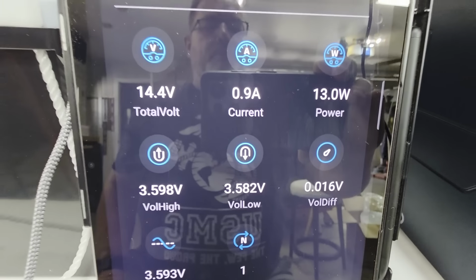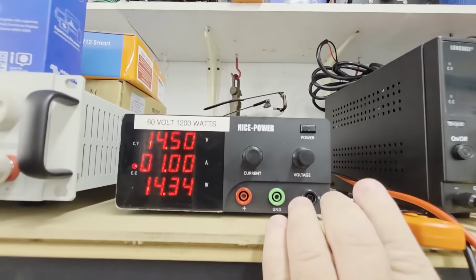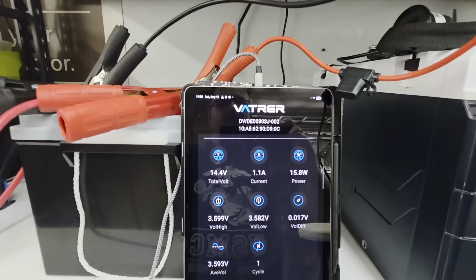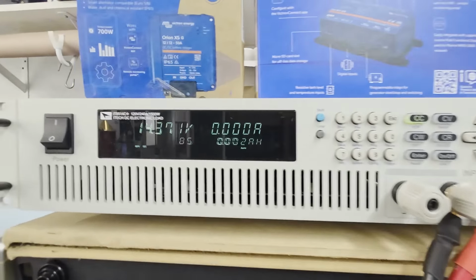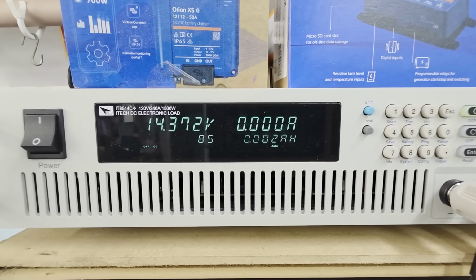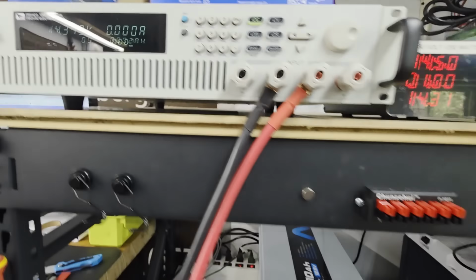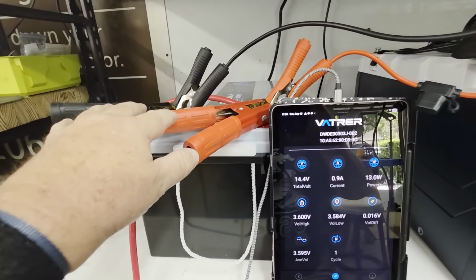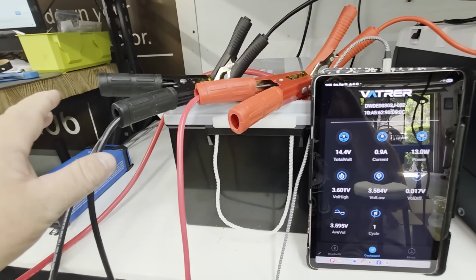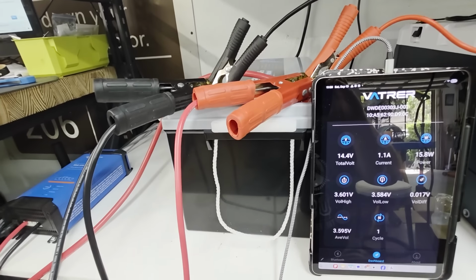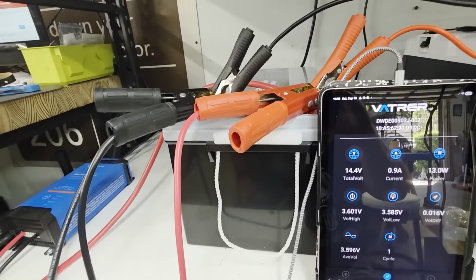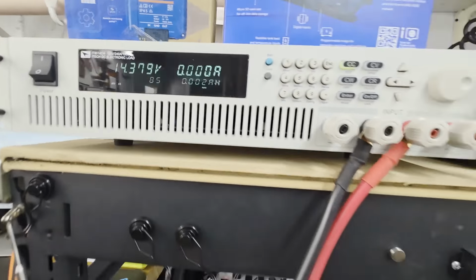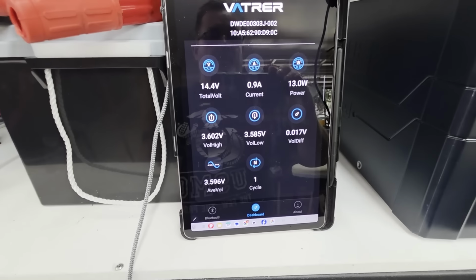So this is good, I'm just going to stop charging here, and we're going to cap check it right from here. I've already got the iTech 8514C Plus hooked up, so we're going to shut off all the chargers. We'll disconnect the charger, so in case there's any kind of backfeeding of current or something, shouldn't be, but just in case we'll isolate it just to the capacity tester, and then we'll do a capacity test right now.